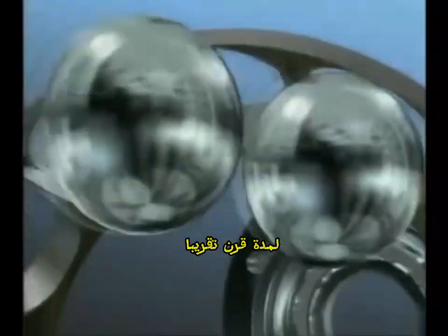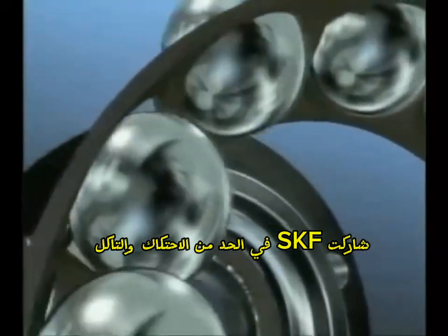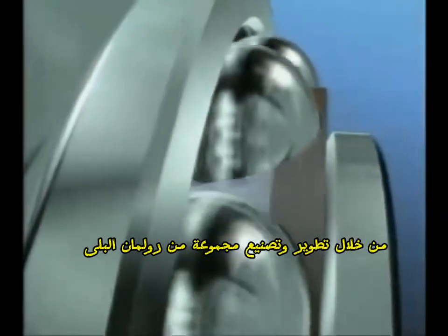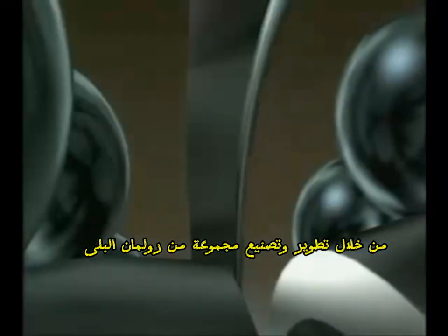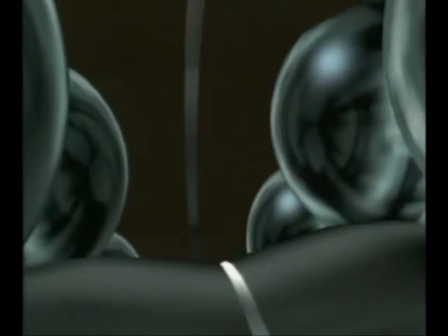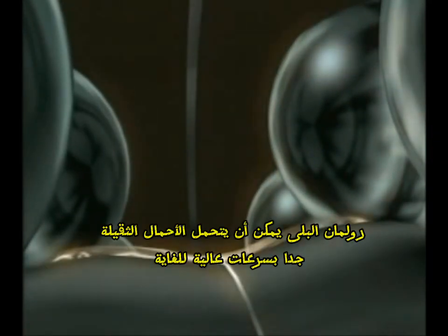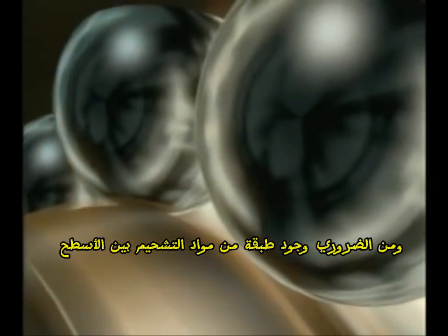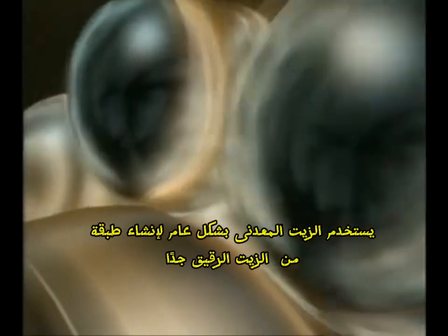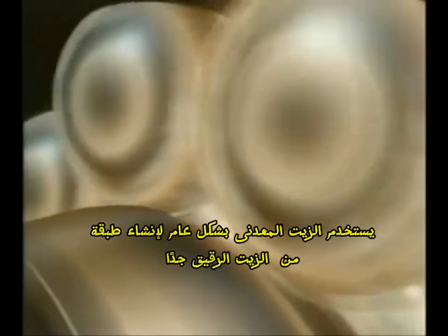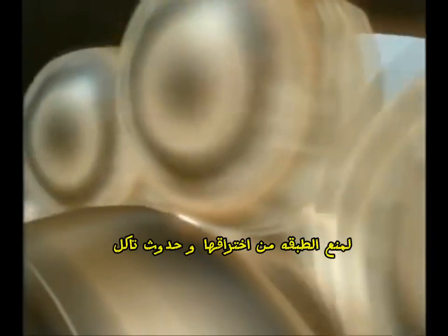For almost a century, SKF have been involved in the reduction of friction and wear by the development and manufacture of a range of rolling bearings and lubricants. Rolling bearings can carry very heavy loads at extremely high speeds, and it's essential to have a film of lubricant between the surfaces. Mineral oil is generally used to create the very thin oil film, which is between 1/10 of a micron and up to 1 micron. Very smooth surfaces and clean conditions are required to prevent the film being penetrated and wear started.